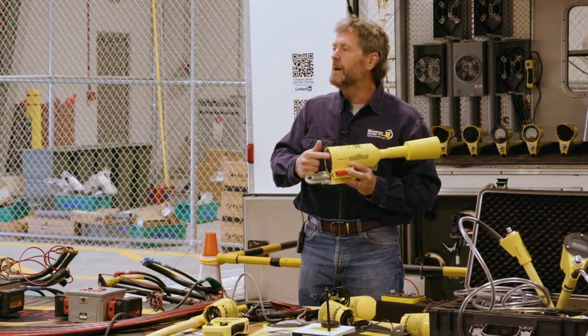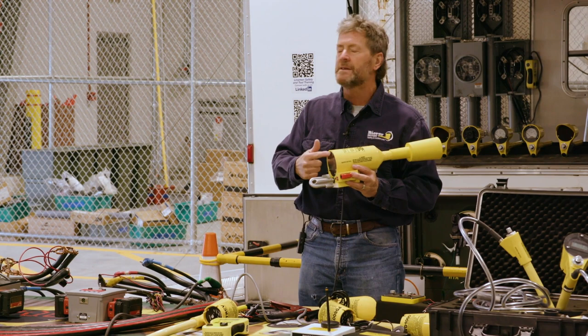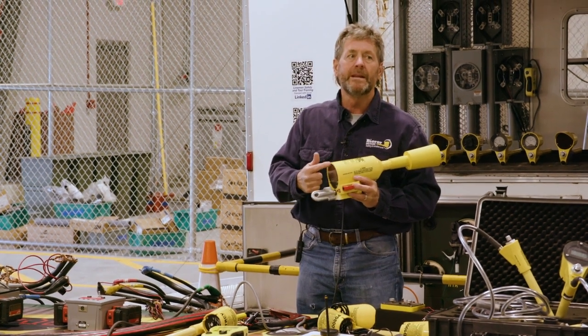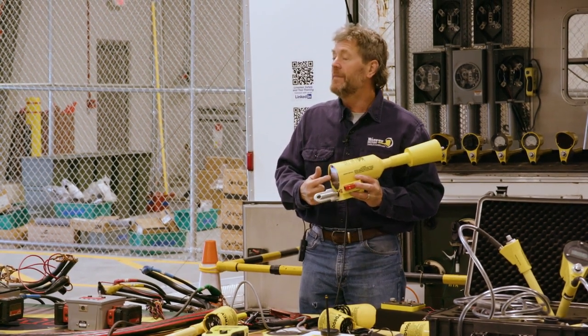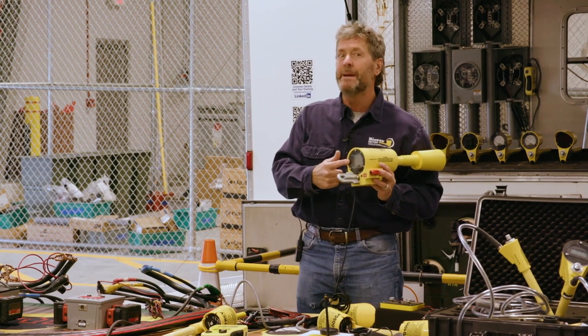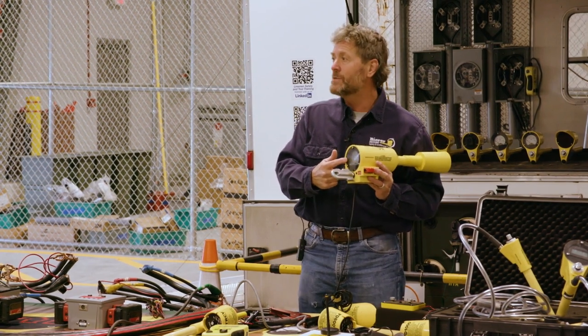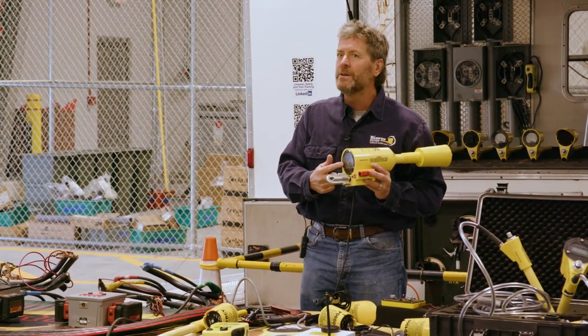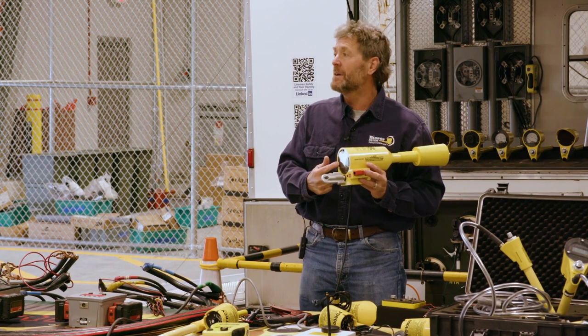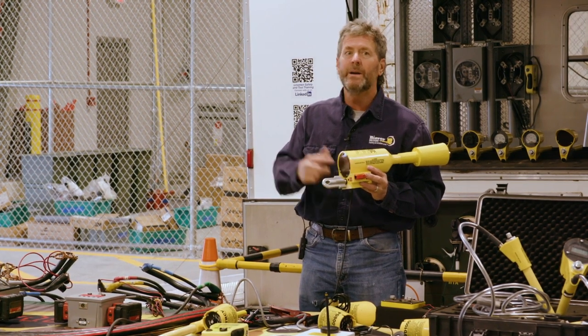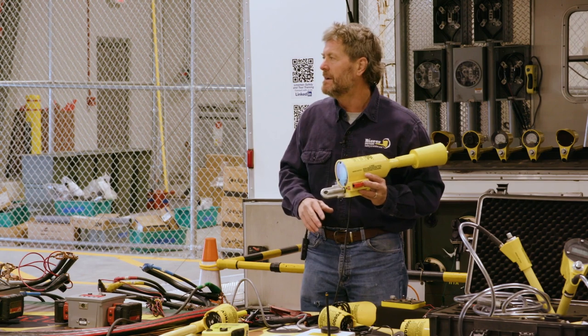If the cable's good, the needle comes down within a few seconds and stays down, the cable's good. If the needle goes up, stays up, or bounces, then the cable's bad. If the needle goes up and hangs at maybe 20%, it's just telling you you have some bleed on the cable. It's an old cable and a long run, but it's fine. Cable's still fine.